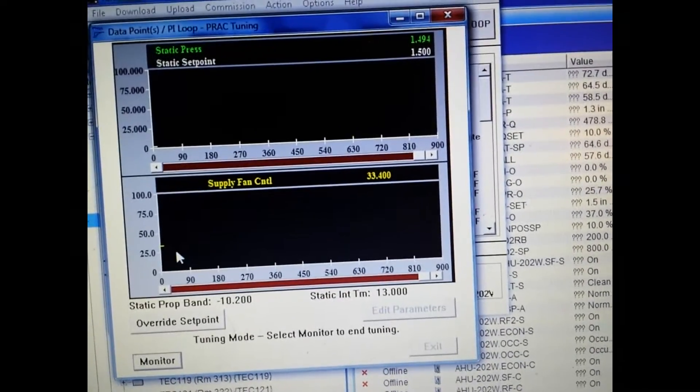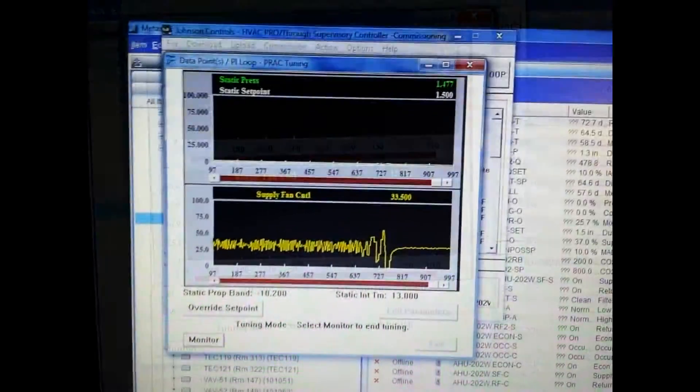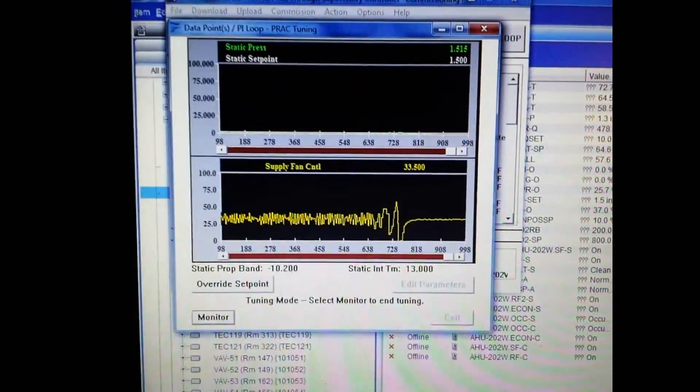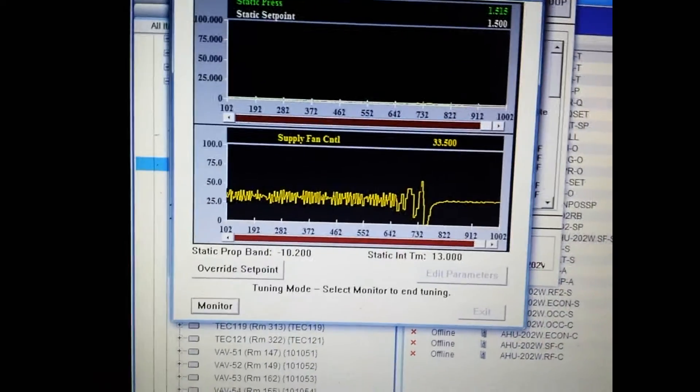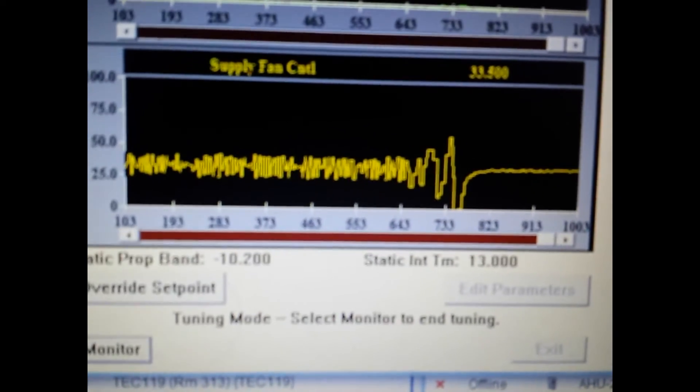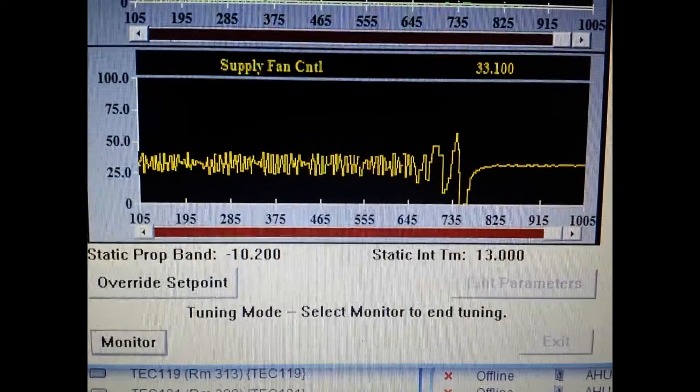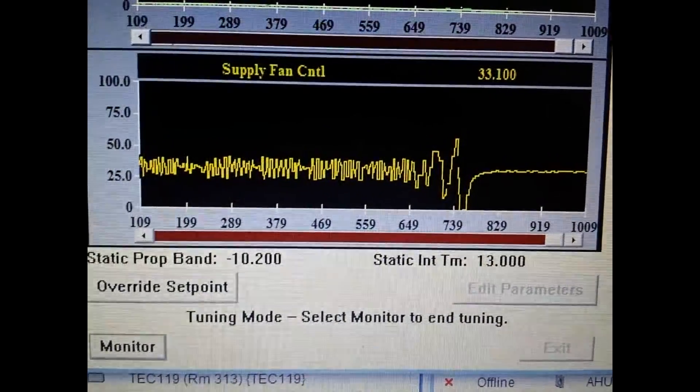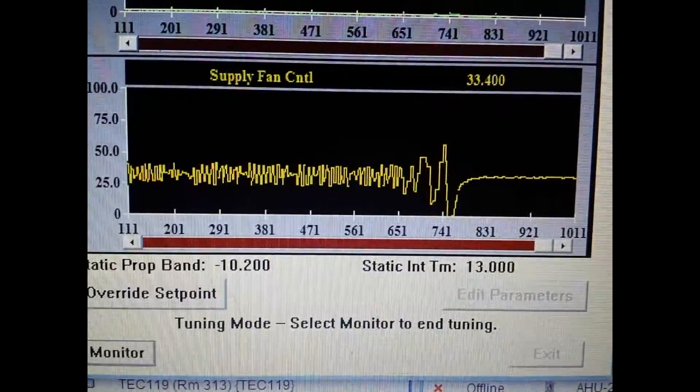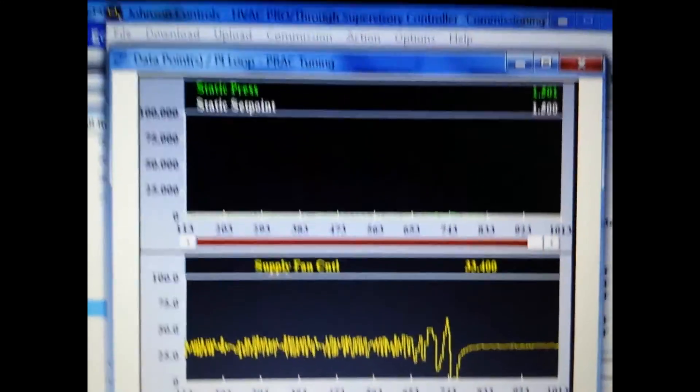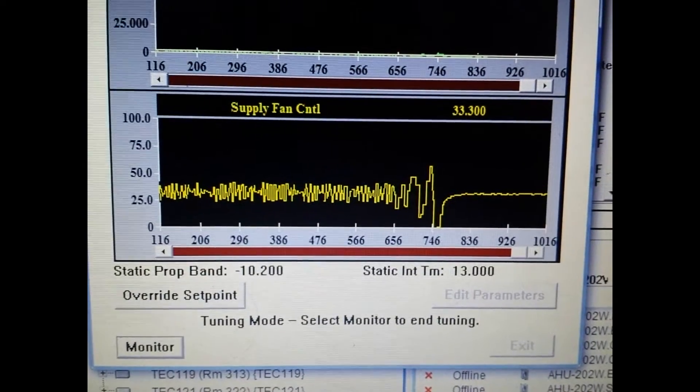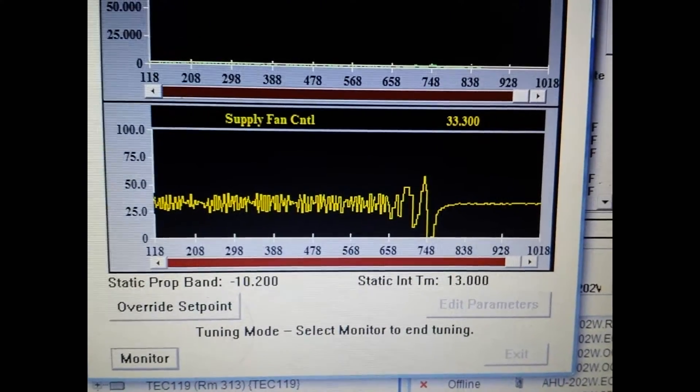And this is where we're actually now tuning. The amount of time that it takes to tune the particular PID loop you're working with is going to vary. Here you can see that after a brief period of time we have a much more stable output from our device. You can see where it has started to adjust the prop band as well as the integral time values, and we have a much more stable output to our drive.